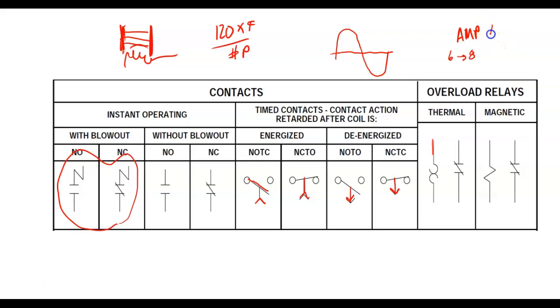The rule of thumb is that the start current, to get it started, is 6 to 8 times your full load current. So if you had a motor that required 10 amps to create its horsepower at its rated voltage, it would take between 60 and 80 amps to do what? Get it started.